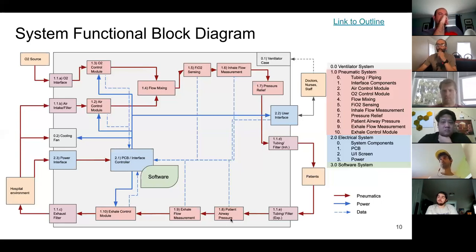On the expiratory limb, we're still planning to have this internal to the device. This is one of the open questions we'll talk about later, but in the interim there's patient airway pressure monitoring, flow monitoring, and an exhale control module, then out to the exhaust filter back to the hospital environment.